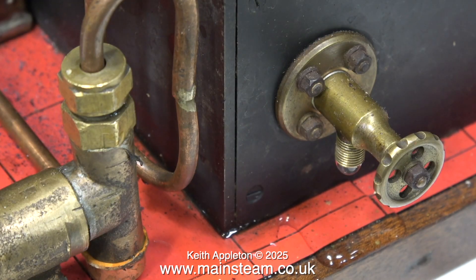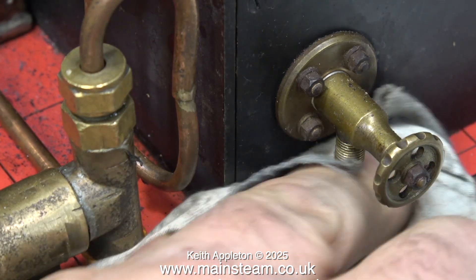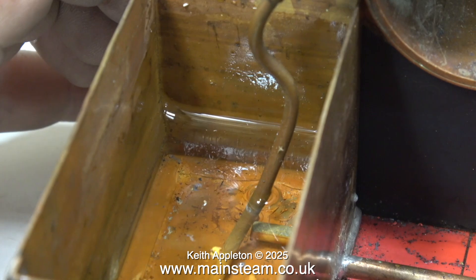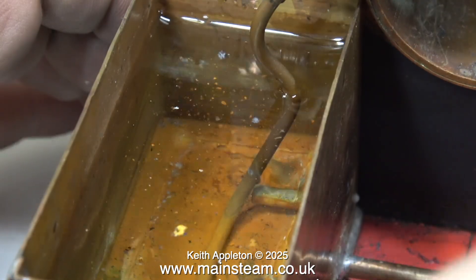This by the way is just a blow down valve — I'm checking that it works and it does. As you can see from this clip, the water level goes down in the tank as I move the handle. This clip is speeded up so you can see it happening more clearly. I still don't quite get the rust, but more about that later.